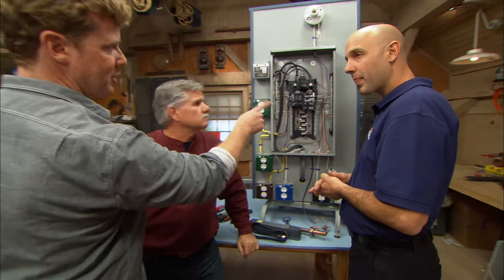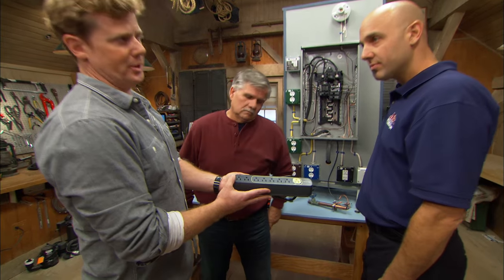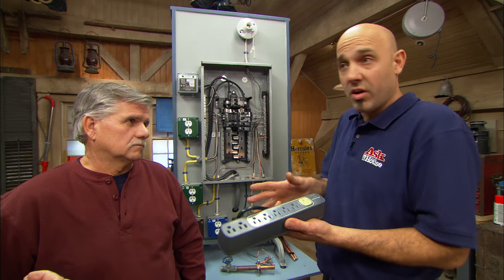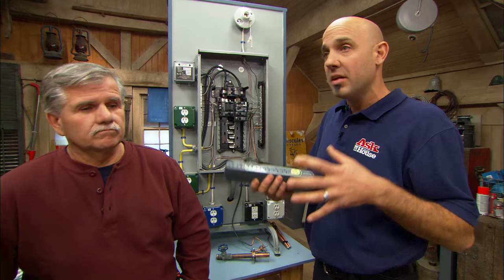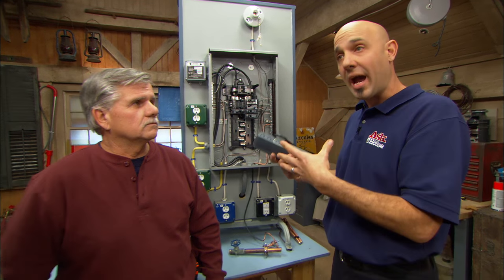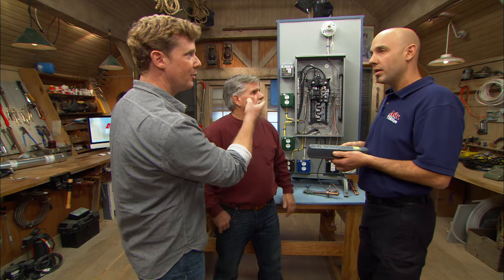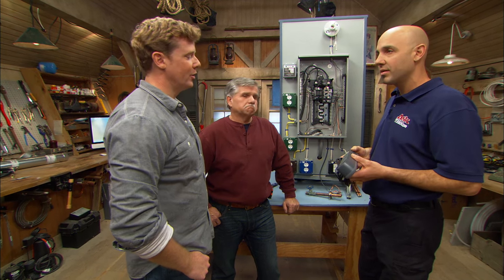If you have whole-house protection either way, why do we also need point-of-use protection? Not all surges originate outside — a lot can originate inside from, for example, a window air conditioning unit. When that unit kicks on and kicks off, it creates surges. When the unit shuts off, the surge comes right back up. Those surges can go directly to a computer because they don't necessarily pass through the panel. These point-of-use devices give the shortest path to ground and protect that specific device.